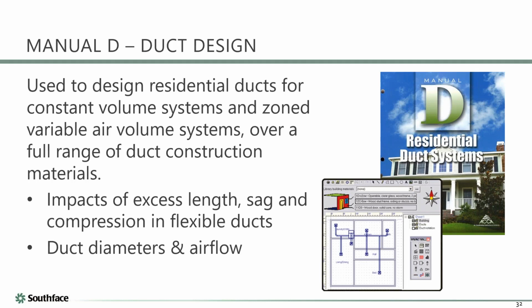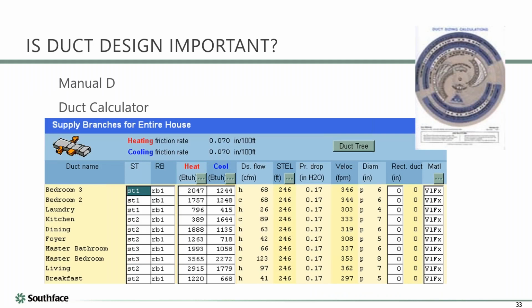Sure thing. Manual D is the process by which we design a duct system, and it starts with a room by room load calc. So we know the heating load and the cooling load on this room right here, and we can back out what is the CFM for heating and what is the CFM for cooling, and the bigger of the two is what we will design the duct for. So each room essentially is designed with a duct system to deliver the bigger CFM of the heating or cooling. So that's the first step. Again, typically we're going to do this with a tool, software, or an old school ductilator.